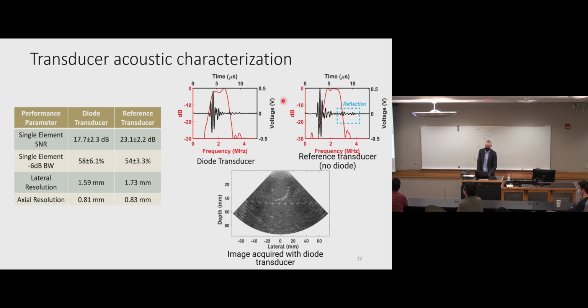And so you can see qualitatively these look pretty similar. The main negative feature that this one on the right without the acoustic diode has is this extra reflection here. This looks pretty small, but when you display the ultrasound image with something like 40 dB dynamic range, then you can start to see these doubling artifacts. And so as you can see, the bandwidth is similar between the two. We actually have a little bit better bandwidth with our acoustic diode. Signal to noise ratio, we definitely lost some with our acoustic diode. And then the lateral resolution is similar between the two different cases.